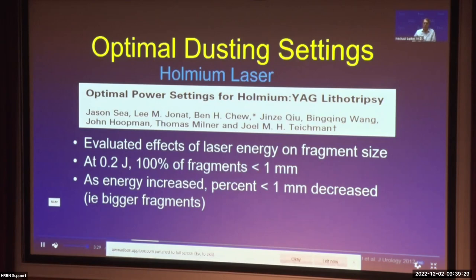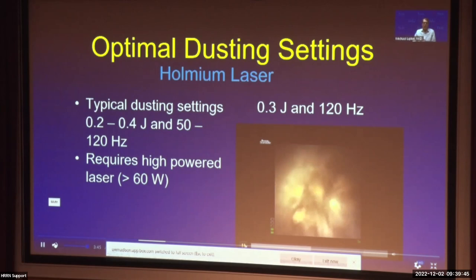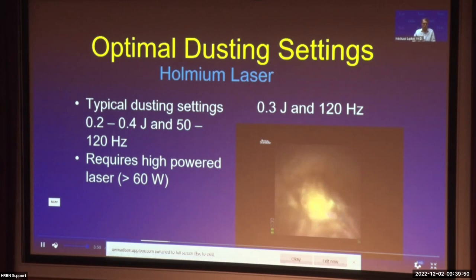For the holmium laser, the dogma is that you need low energy to create small fragments in order to effectively dust. To be efficient, we then needed to use higher frequencies. This is a video of dusting with a holmium laser at 0.3 joules and 120 hertz, which is 36 watts. Typically we use settings between 0.2 and 0.4 joules, sometimes up to 0.5 joules, and 50 to 120 hertz, requiring a high-powered holmium laser.